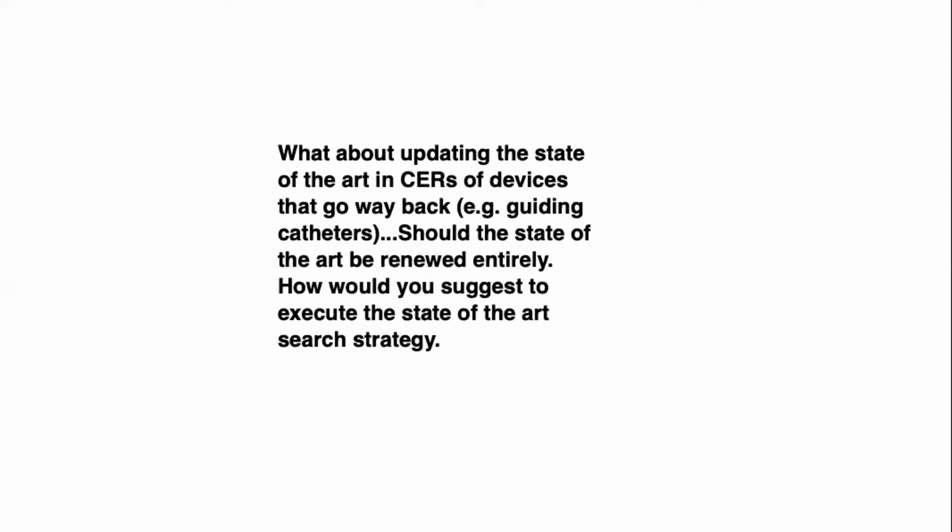And most importantly, the state of the art then goes into defining and presenting the safety and performance outcomes, and gleaning acceptance criteria from competitor or pooled devices, pooled data and devices.